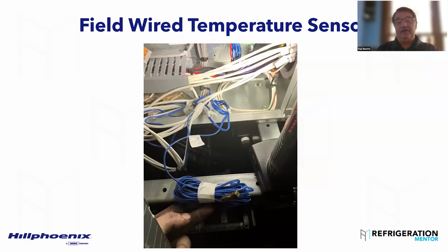So this sensor and the one in that last picture are the exact same job. I got a call from a customer whose system had been running for 3 weeks, and 10 people looked at it and couldn't figure out why we were having so many problems with it operating. I got a call at 9 o'clock on a Friday night. I started talking with them and asking for pictures. When I got that one picture down below, a close-up, it had one sensor. So we literally had the fan drop leg HPV sensor sitting in the cabinet right there.